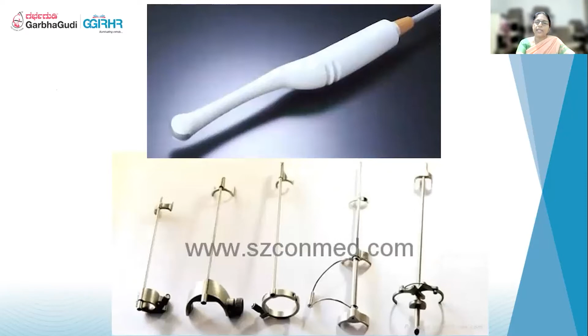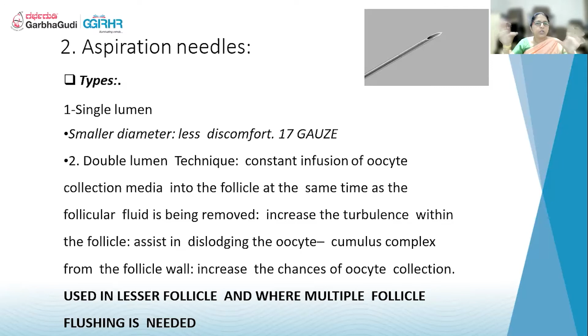Aspiration needles, there are single lumen and double lumen. You might have watched the flushing of the follicles also. When you want flushing in poor responders, you have to use a double lumen technique where you aspirate the follicular fluid and in the other channel you flush the pre-calibrated Ringer lactate. So repeated flushing will break the oocyte cumulus complex, dislodge it and get it for you, because you are having a very poor response. When there is good response, you can use single lumen also.